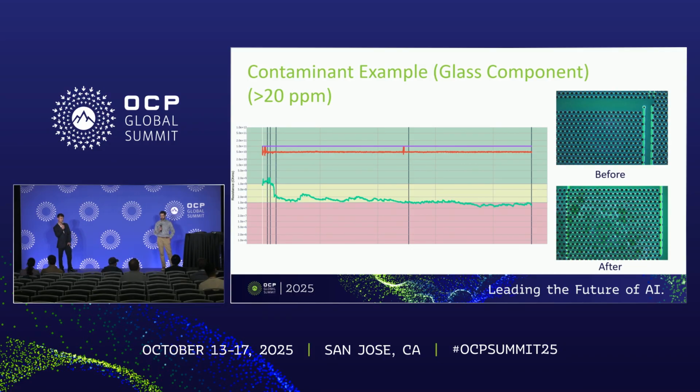We also charted surface insulation resistance over the course of this test. That green line there represents the component. You can see that there was a sharp decline in resistance and then a slow decline into that red shaded region. We use that decline in resistance as evidence that some conductive residue has appeared on the measured surface of the board. The two lines at the top there that did not change actually represent portions of the board where we did not observe deposited residue.